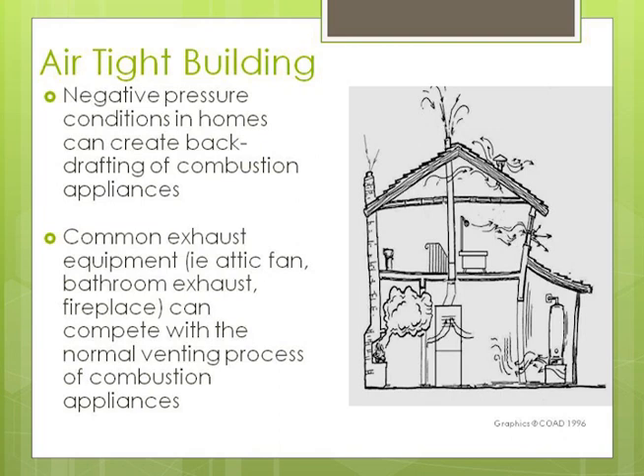We've talked about negative pressure and the kinds of things it can cause — flame rollout, smoke coming into your house from your fireplace rather than going up the chimney — that sort of thing that can happen if you have too much negative pressure in your house. We also talked about the problems with positive pressure in our climate: pushing moist air into walls where it condenses, which is why exhaust ventilation is often a better idea than supply ventilation.